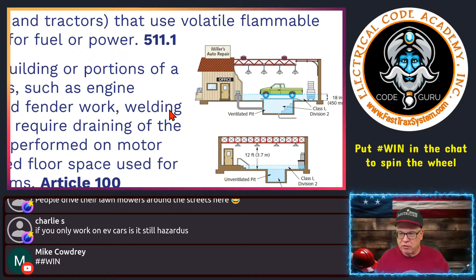So 18 inches up is a Class 1 Division 2 location. At the pit it may be Class 1 Division 1, but what can we do to reduce that area and drop it down so we're only dealing with a Class 1 Division 2 location? If we ventilate it, we can change the type of wiring methods we run, and that ultimately saves money - easier wiring methods to deal with, more options, right?